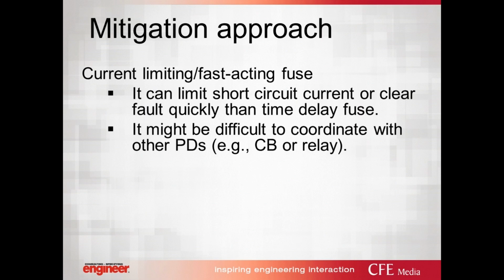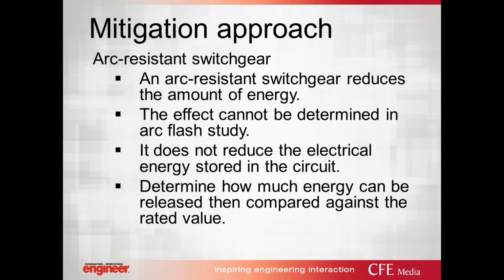The next approach would be a mitigation approach based on the current limiting fuse and fast acting fuse, which we're able to utilizing this one in the short circuit for more reducing the time delay. It may be difficult. Again, one of the problem with that one would be the PD that coordinate with the other devices utilizing this current limiting fuse. The next approach is the arc resistant switchgear.